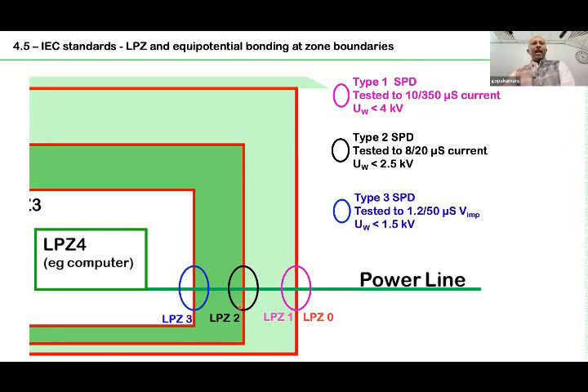The second one, the black color, is at the sub-distribution board. Technically, it's called zone 1 to 2. Here you have to put a type 2 SPD, and that type 2 SPD should limit the voltage to less than 2.5 kV. The first one should limit the voltage to less than 4 kV, because in this location, the LPZ1, the electrical equipment, the fixed part of the installation, can withstand only 4 kV. I told you at the beginning, voltage impulse withstand testing. The equipment can withstand only 4 kV, so the device should limit the voltage to less than 4 kV. Less than 2.5 kV and less than 1.5 kV.